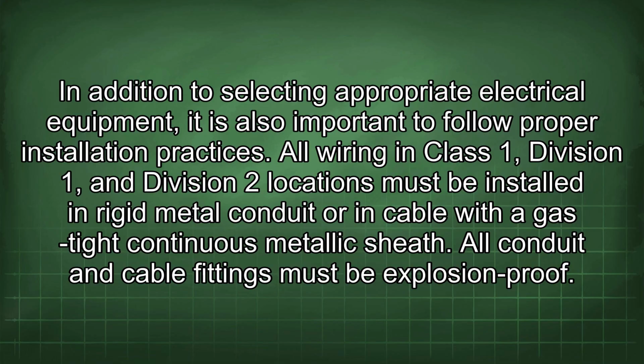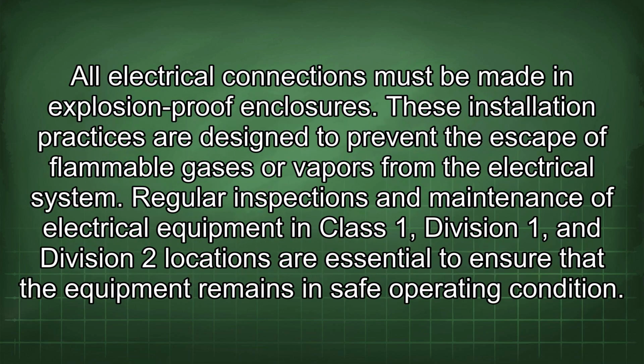In addition to selecting appropriate electrical equipment, it is also important to follow proper installation practices. All wiring in Class 1, Division 1, and Division 2 locations must be installed in rigid metal conduit or in cable with a gas-tight continuous metallic sheath. All conduit and cable fittings must be explosion-proof. All electrical connections must be made in explosion-proof enclosures. These installation practices are designed to prevent the escape of flammable gases or vapors from the electrical system.